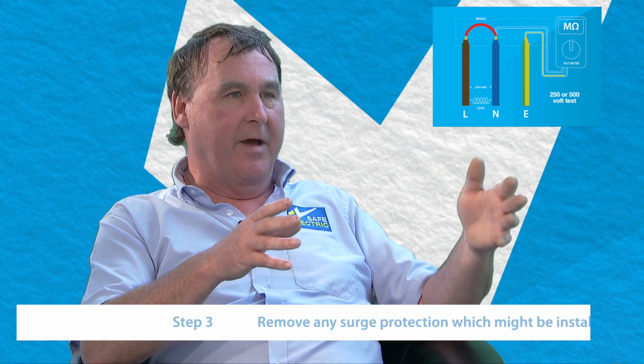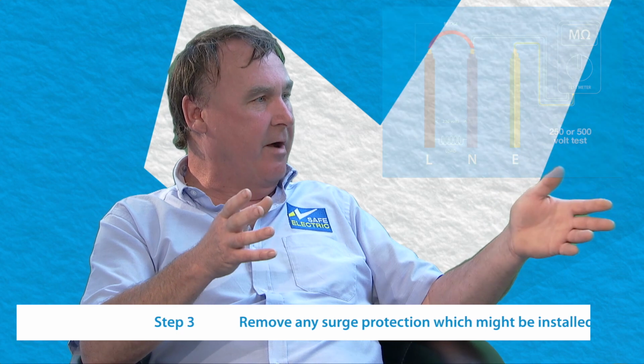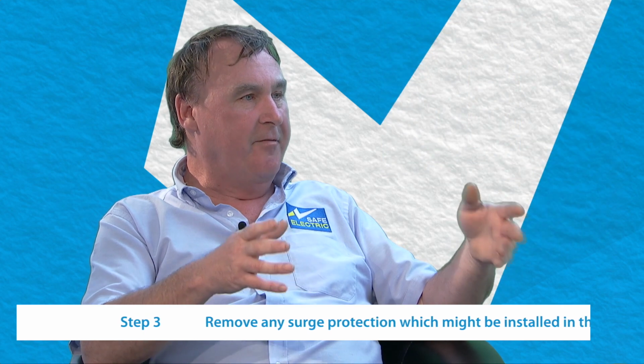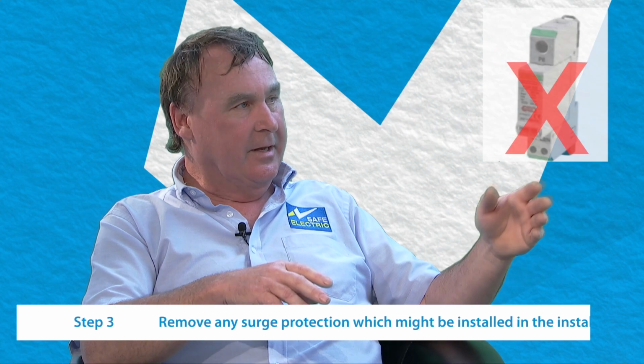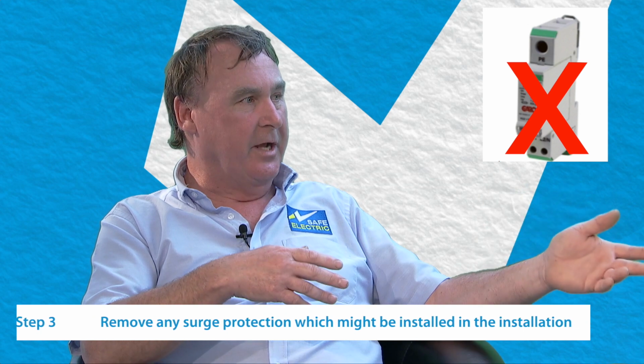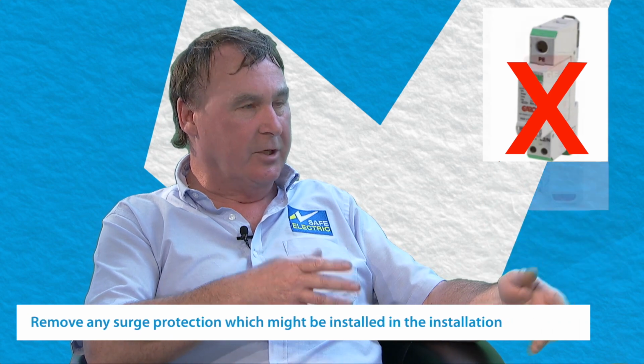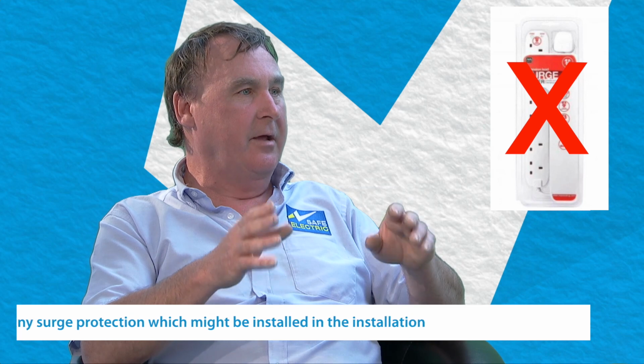Step number three is to remove any surge protection temporarily out of the installation, even down to an extension lead that you might have plugged in somewhere with surge protection built into it. Surge protection will give you an incorrect insulation resistance reading. Normally, if you see 0.4 of a mega ohm, you can nearly be sure there's surge protection in the circuit somewhere. Won't do any harm if you forget this step, but you won't get the correct reading.